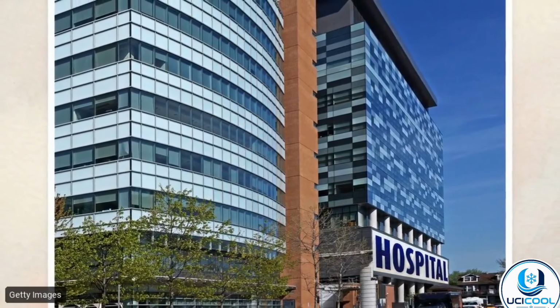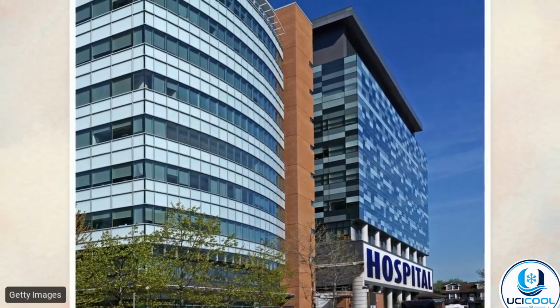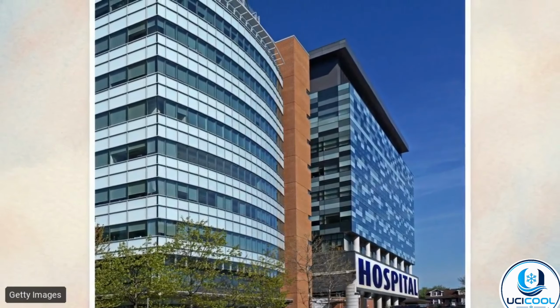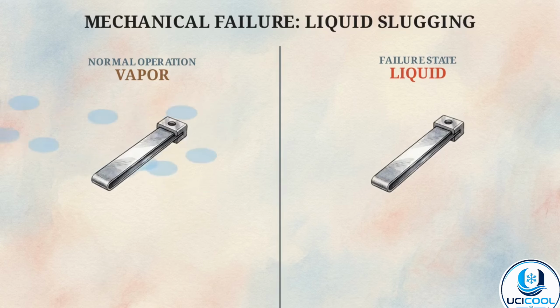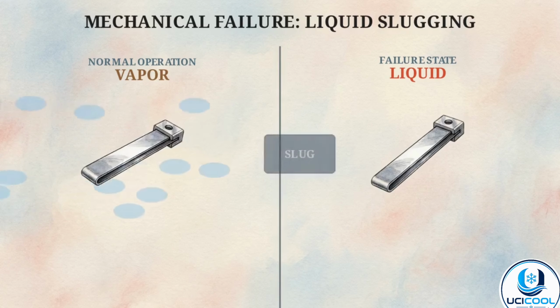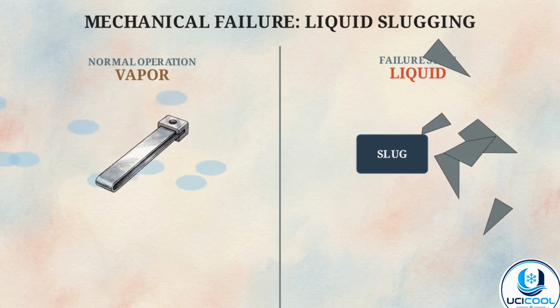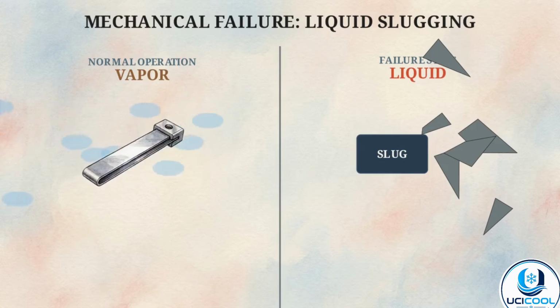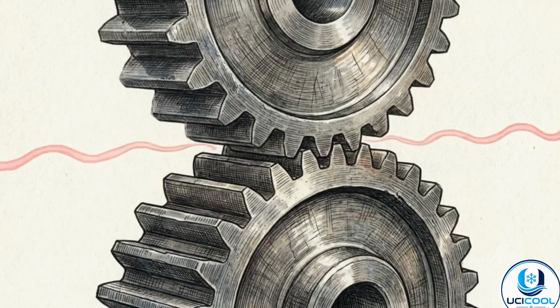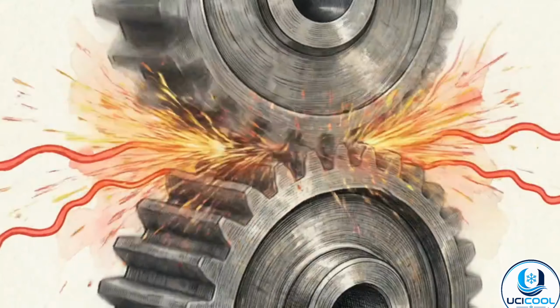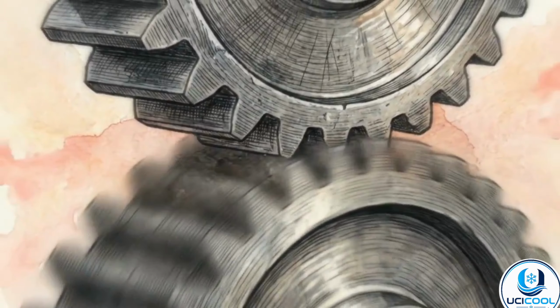In a hospital, where temperature control is a safety requirement, these compressors are vulnerable to the wear caused by constant friction and heat. A common mechanical failure is known as liquid slugging. Because compressors are designed to handle vapor, any liquid refrigerant entering the chamber can impact the moving parts with enough force to shatter the internal valves. If the internal components seize, often due to a shortage of oil, the motor may experience a locked rotor. The motor attempts to turn the stalled mechanism, causing a spike in electrical current that can lead to a complete system shutdown.